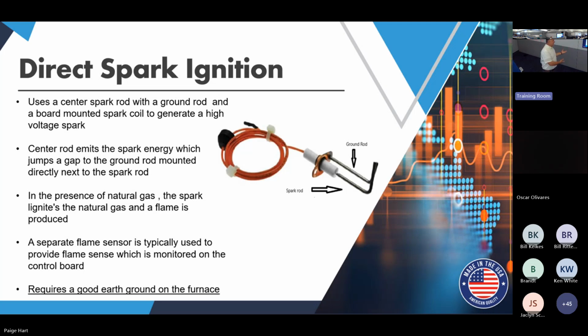We have a spark rod. This is a lot like what you see on a gas grill: it has a sparker where you press the button, it goes, and you get that little spark. Same idea here. You have a control board with a little spark coil on it, and that spark coil sends out thousands of volts, usually in the kilovolt range. The reason it has to be such high energy is that it has to jump a little gap between a ground rod and the center rod in order to make that spark. That's why you have to have a good earth ground. It's very important when you're using spark ignition control boards that the house has a good earth ground.